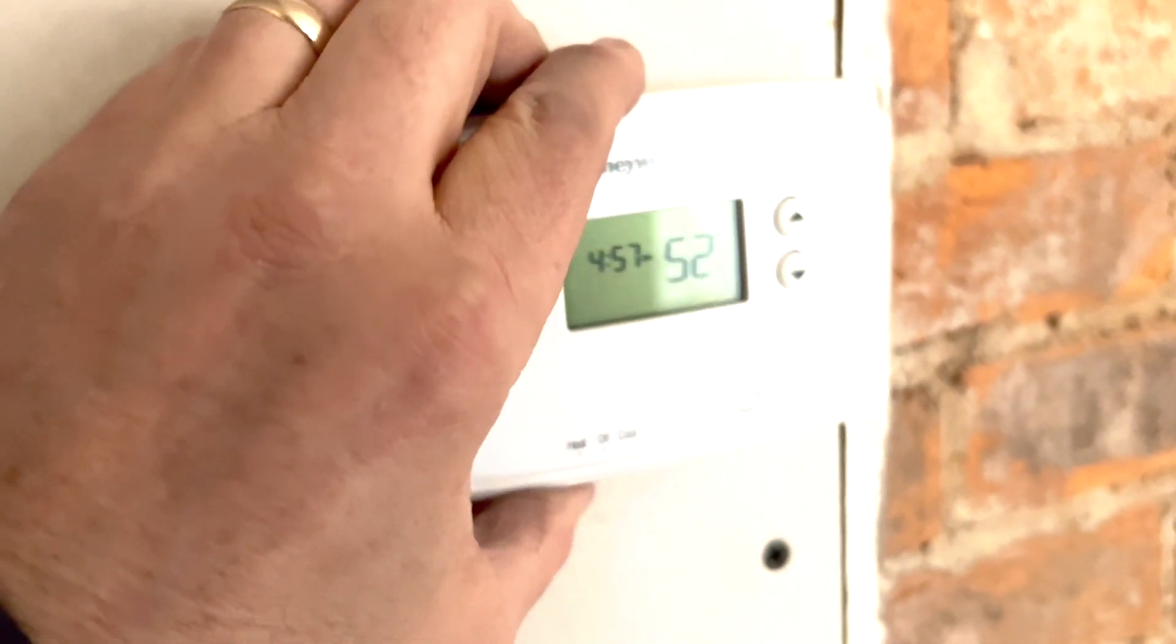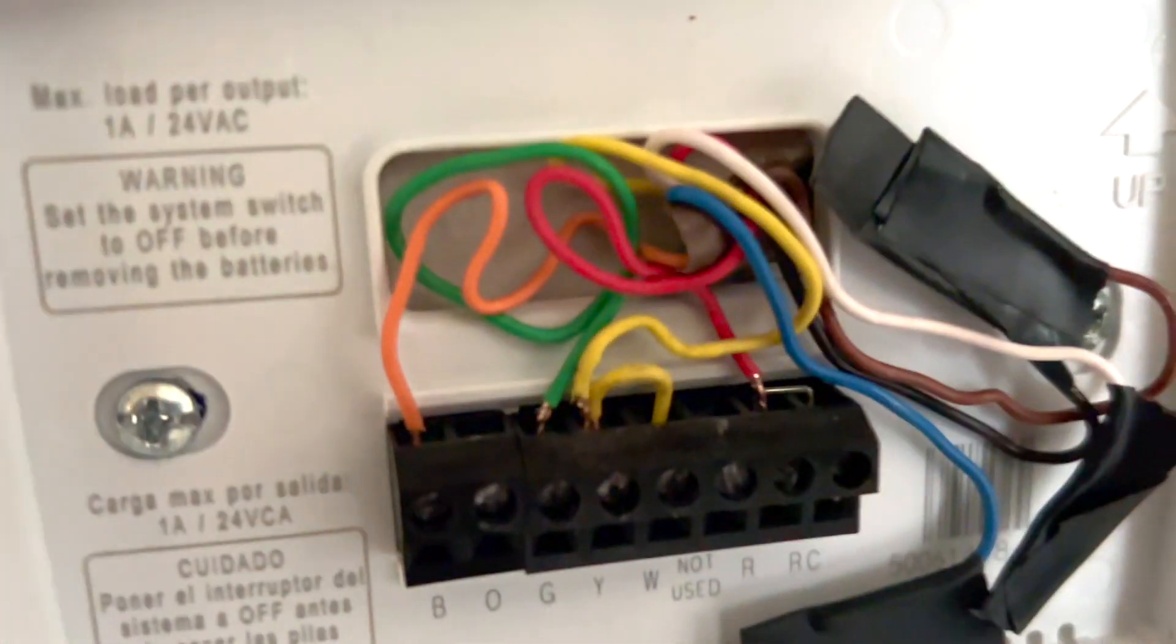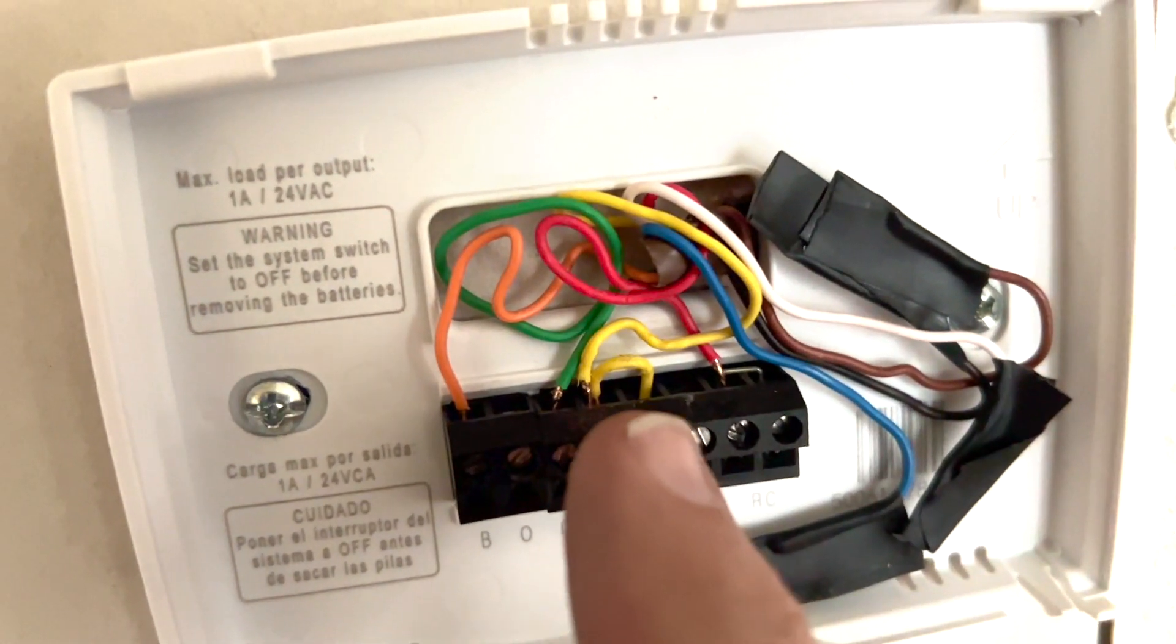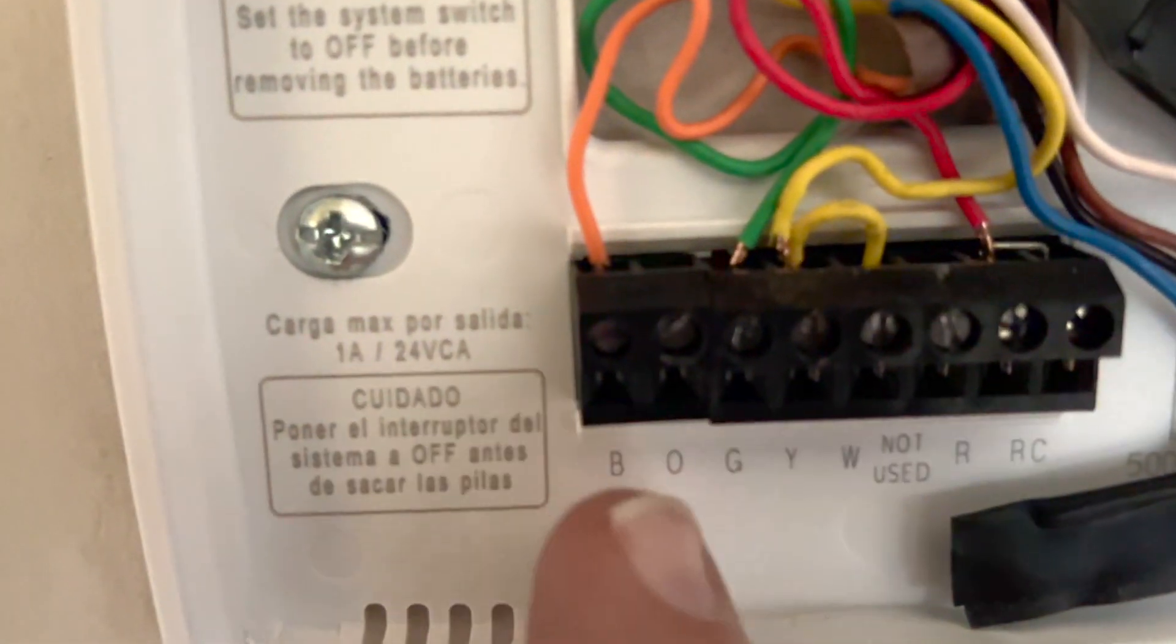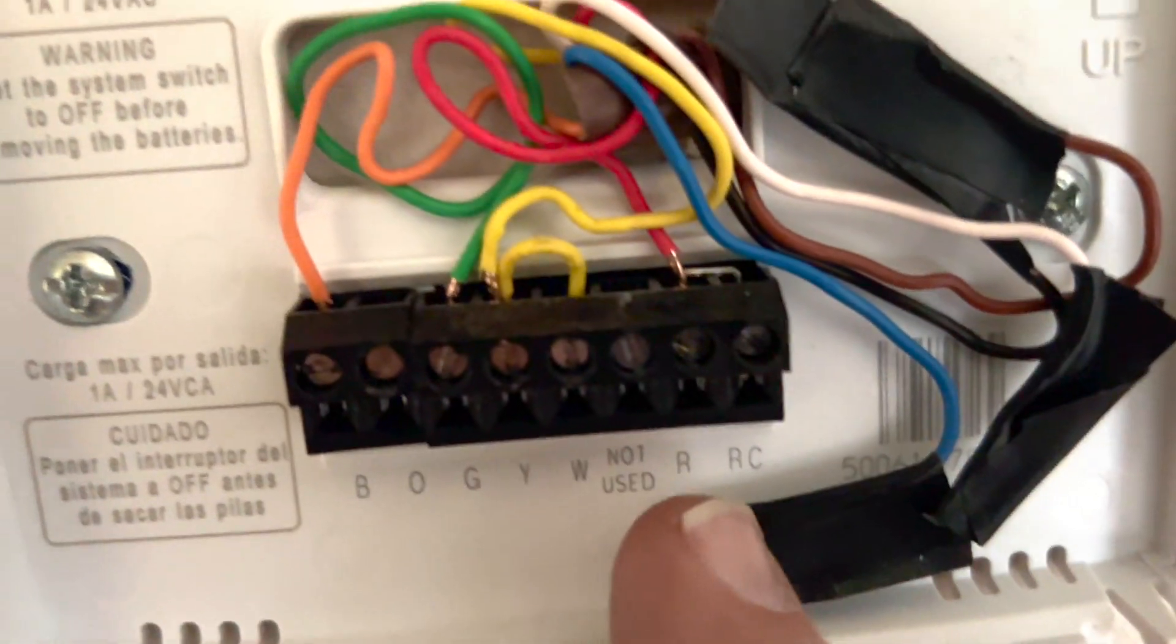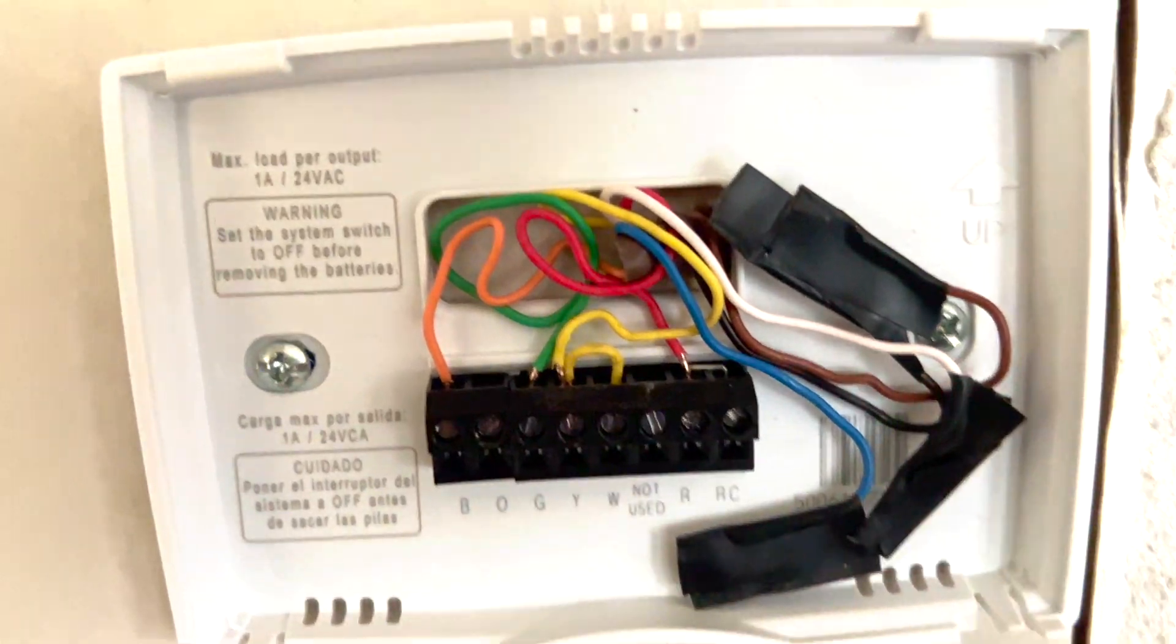Here's the thermostat setup. Here's our Honeywell thermostat and you see the temperature is 52. We started today at 47. So that's the final wiring and we'll go up close. You can see we've got a jumper between yellow and W—that was per the thermostat instructions. We've got our orange for the reversing valve, green, yellow, and red for the power. That's how we wired the thermostat.